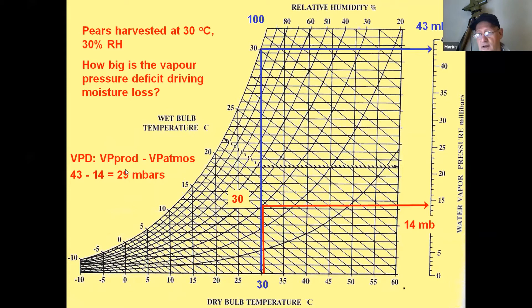We then put it in the cold room at 0 degrees Celsius, 90% humidity. It's still going to be losing moisture. The fruit has not changed temperature. It's just gone into the cold room. So the fruit is still hot. So it's still running at 43 millibars. But the environment has now changed. We're now in a cold room at 0 degrees Celsius with a relative humidity of 90%, the second line from the top. And if we look at it across to the right, that's 6.5 millibars of vapor pressure. In other words, what it's telling us, because the temperature is low in the cold room, even though the degree of saturation is 90%, it's still only 6.5 millibars of moisture or vapor pressure.